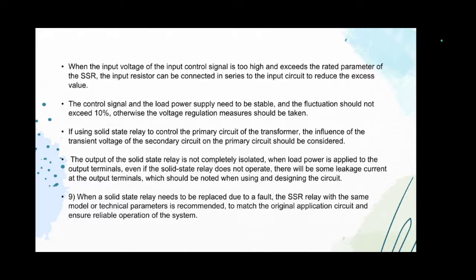Number 8. The output of the solid-state relay is not completely insulated when load power is applied to the output terminals. Even if the solid-state relay does not operate, there will be some leakage current at the output terminals, which should be noted when using and designing the circuit. So, we should keep being reminded that even if the SSR is not operating, there is leakage current at the output terminal. And during maintenance, we should cut off the power supply before proceeding to check the output circuit.